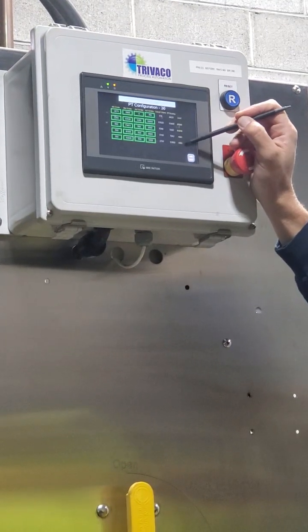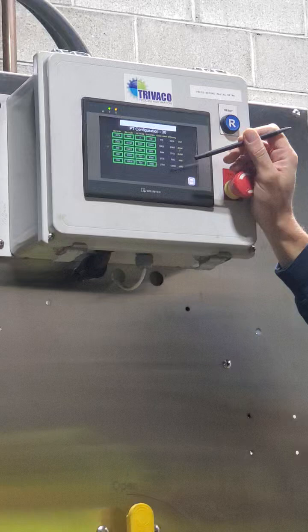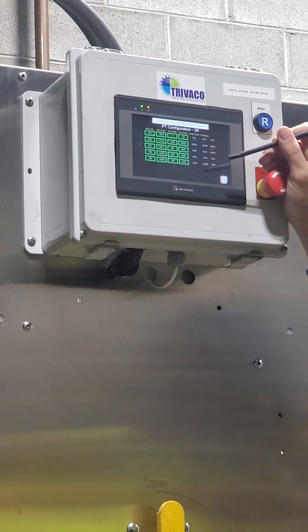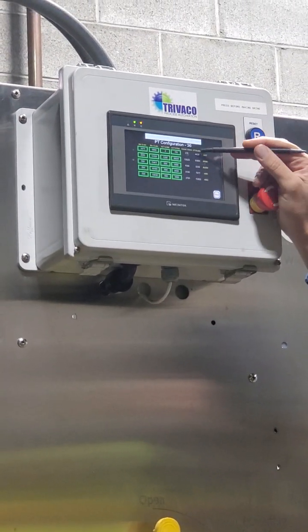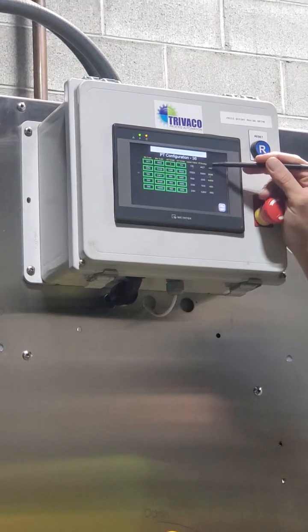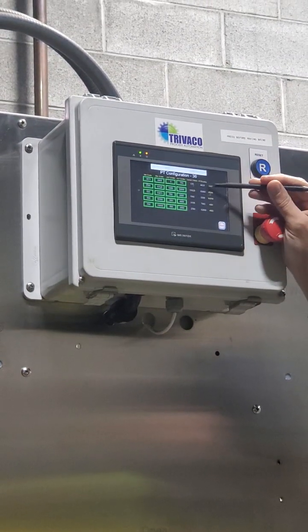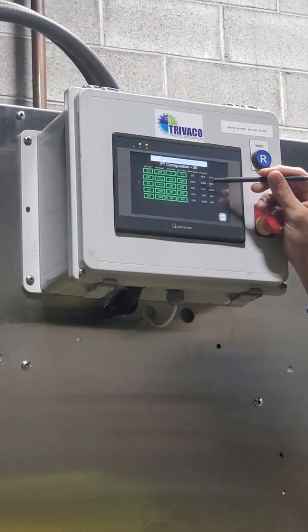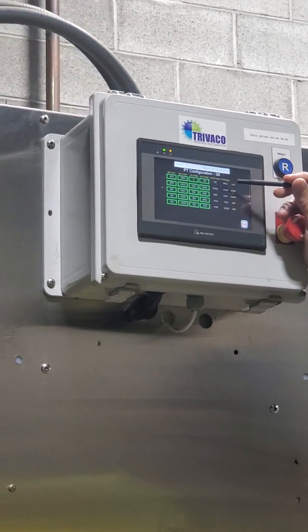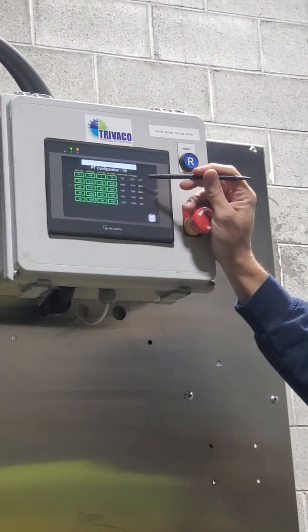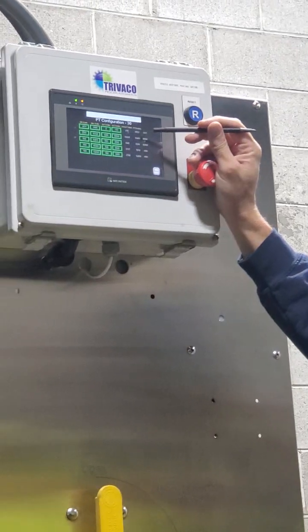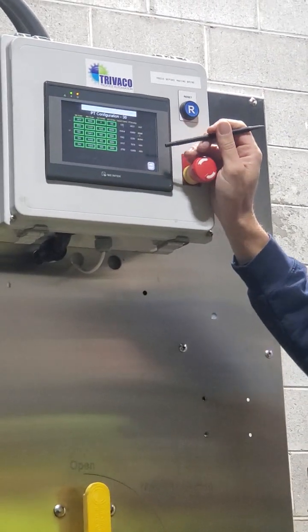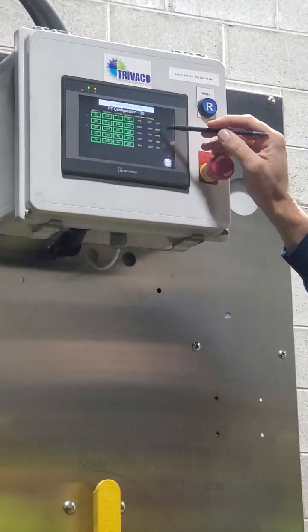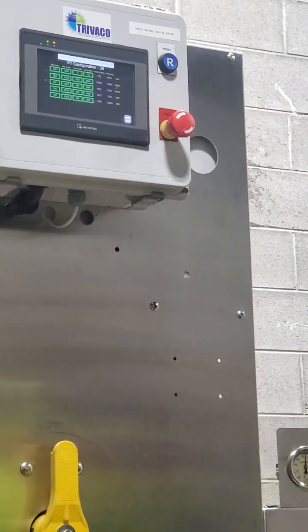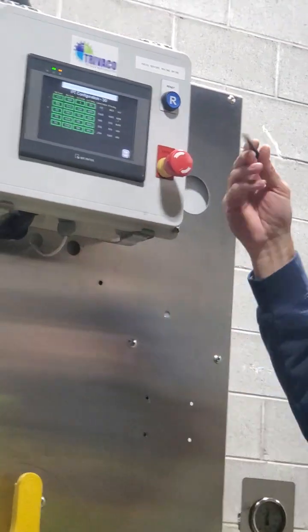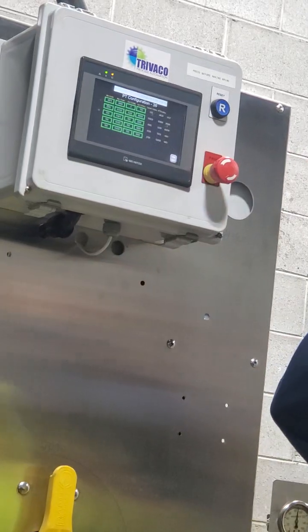Yes, we're in the brine. So if something's not working, like let's say the salt tank adds water and nothing's going up, this is where you want to come look to see if that's 3200, because that means your transducer probably failed. Some electrical connection went bad, either the wire got pulled out or something happened where the pressure transducer is not giving you a reading. So that's 3200. That's the key number on those. So that tank back there, when it wasn't working, it said 3200?